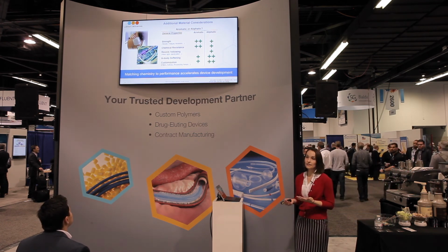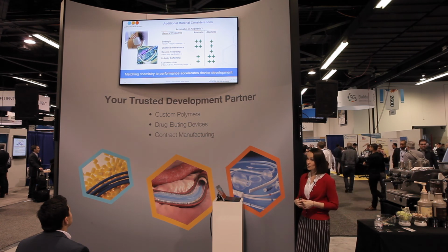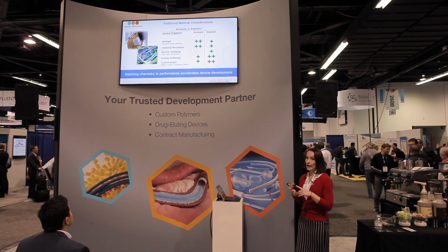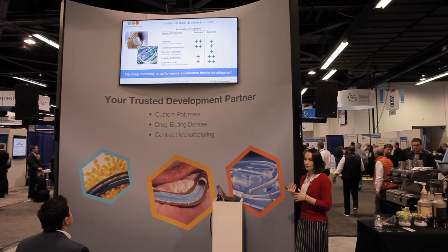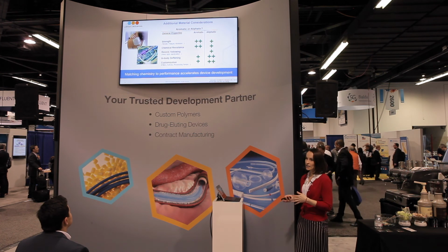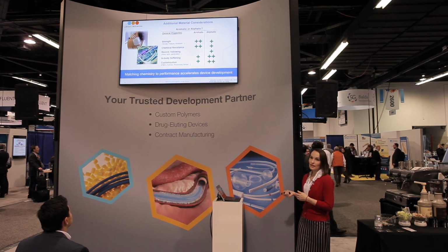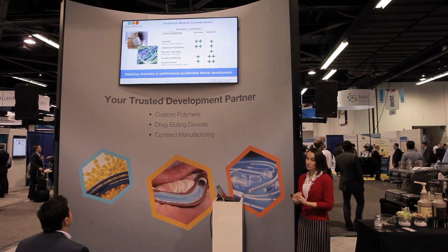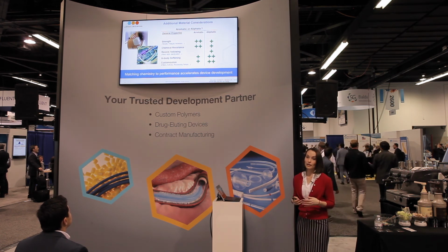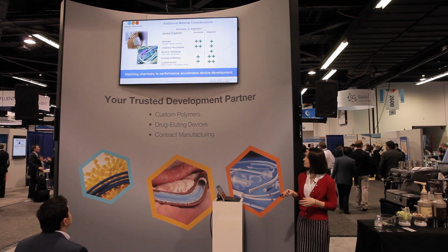And the last thing is, if you're thinking about customizing a material with a high loading of radiopacifiers, you're looking for flexibility on your thermal processing windows, or looking for a more highly customized product, the aliphatics tend to take fillers much more easily, and they do tend to have a wider extrusion and processing window, so they may be a good option there.